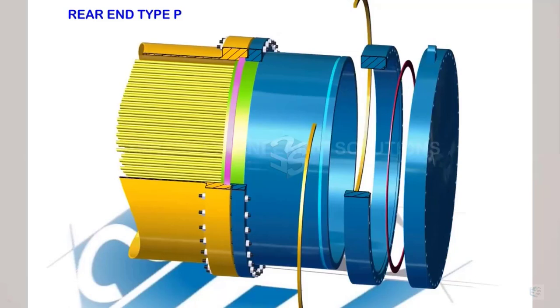For the shell side: the magenta color represents the gland packing, which is placed on the top surface of the tube sheet. The green color piece is the tube sheet. The shell side flange has a groove inside which the gland packing sits. The blue color flange has a tongue or raised face arrangement. When the nuts are tightened, the gland packing gets compressed. During thermal expansion, the tube sheet along with the tubes and channel shell moves to the right, but the compressed gland prevents any shell side leakage.